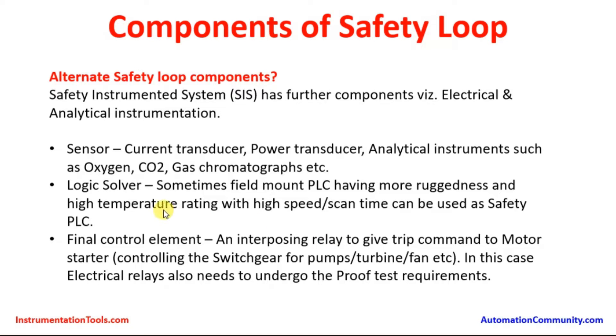Alternate safety loop components: the Safety Instrumented System also includes electrical and analytical instrumentation. Earlier we saw process-related sensors and final elements, but there are other components as well. For sensors, there are current transducers, power transducers, and analytical instruments such as oxygen analyzers, CO2 measurement devices, and gas chromatographs. These are used in refineries, petrochemicals, and other chemical industries.